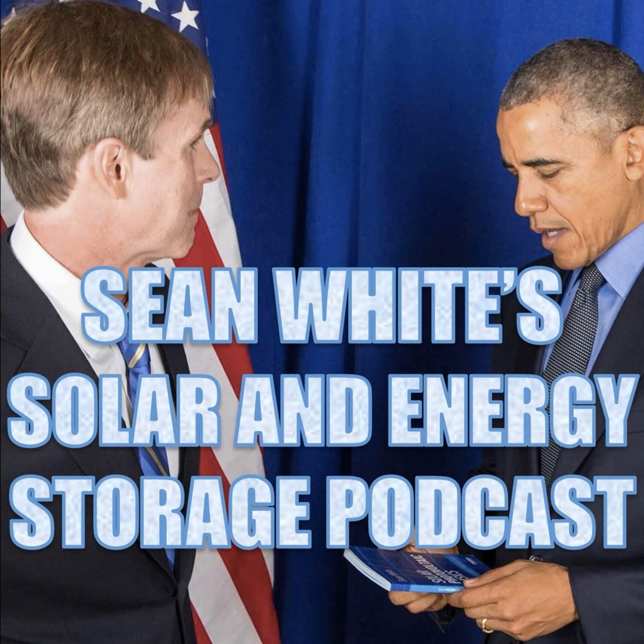The title, Solar PV system is equipped with rapid shutdown, shall utilize capitalized characters with a minimum height of 9.5 millimeters, 3/8 of an inch, in black on yellow background, and the remaining characters shall be capitalized with a minimum height of 4.8 millimeters, 3/16 of an inch, in black on white background.